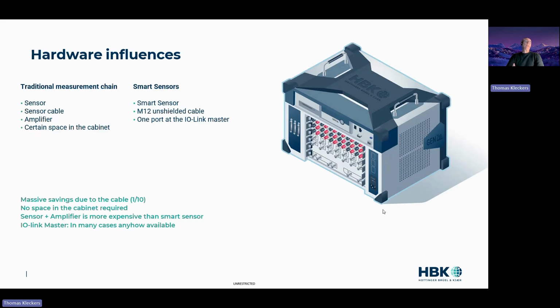If we talk about hardware, a traditional measurement chain consists of a sensor, the sensor cable, the amplifier, and if you have the cabinet system, you need also a certain space in the cabinet. And if you compare that directly with the new smart sensors, you can see you just have to buy the sensor. The cable is much, much cheaper. It is a standard M12 cable, not a special bridge measurement cable. And the only thing you need is one port in the IO-Link masters. And normally IO-Link masters have more than one port. We're talking about 8 ports. So cost saving is massive due to the cable, due to the fact that you do not need any space in the cabinet, and due to the fact that the sensor and the amplifier system in one housing is much more cost effective than separate components.